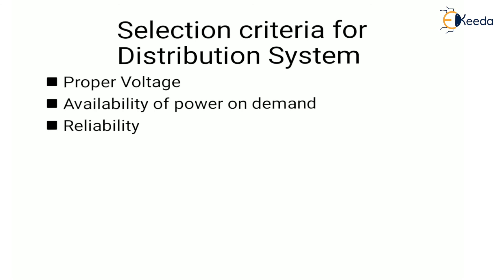Next is the selection criteria for a distribution system. The first criterion is proper voltage — a distribution system should ensure that the voltage variations at the consumer terminal are within permissible limits. The statutory limit of voltage variation is plus or minus 5% of the rated value at the consumer's terminal.